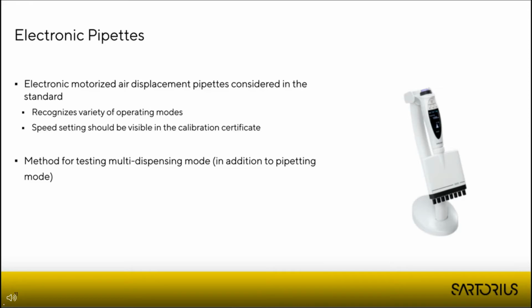Then one big addition as well was the inclusion of electronic pipettes. Electronic pipettes are now included in one of the annexes to the standard, which is very good because now the standard recognizes that there are multiple different pipetting modes, so how you can use the pipette. Previously, the standard only recognized forward pipetting as a standard method of testing pipettes, which is still the case, but there was no mention of electronic pipettes and the capabilities they offer.